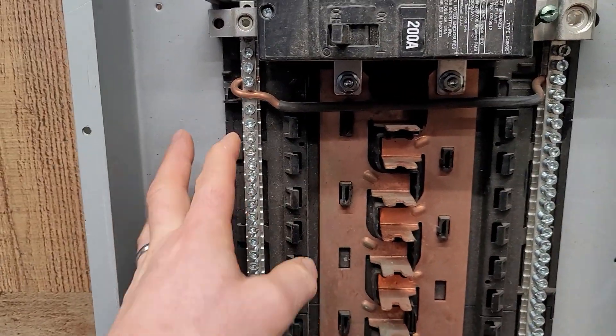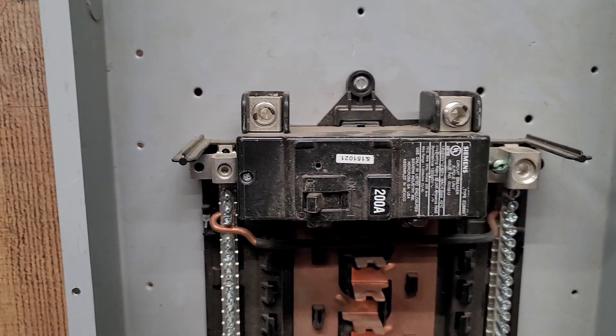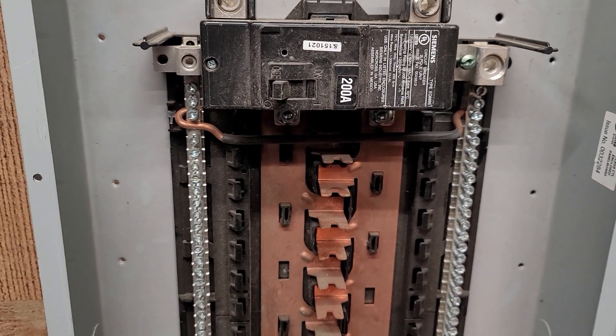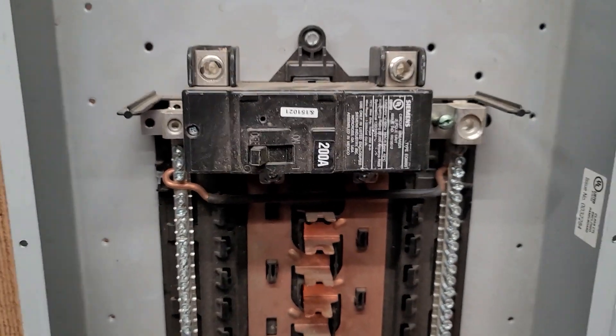So ultimately what you want to make sure that you do is that you separate the grounds and neutrals if you're past that first point of disconnect in your system and to make sure that you still bond the frame of your can when you're doing all this.